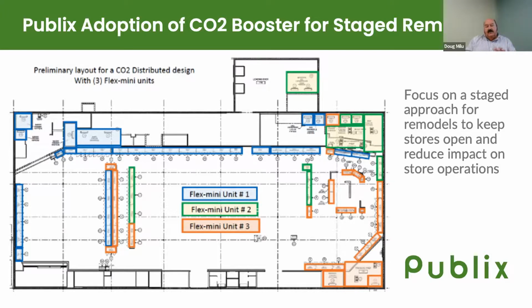This store will have 3 units that will go in the existing machine center. Each unit will be low temp and medium temp, so basically split suction. That gives me 3 different options within 3 different machines to divide up my sales floor, so if I have an issue with a frozen food freezer, I've got a meat freezer and an ice cream freezer I could move product to. So when you check the box on redundancy, this system helps us get there.